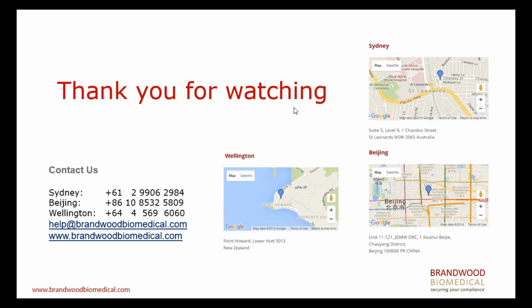Now, the first question I've got asked, one of them is, do you need the EC certificate to go through the TGA assessment? Okay, so in this case, if you've got a device that's got a medicine or animal microbial origin or is listed under the exclusion, basically if your device can't use the EC certificate and you must go through TGA, you don't necessarily need the EC certificate to apply to go through TGA, but if you do have that certificate, you can use it to abridge the assessment fees and potentially timelines.